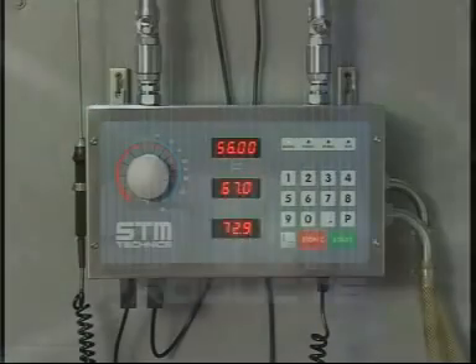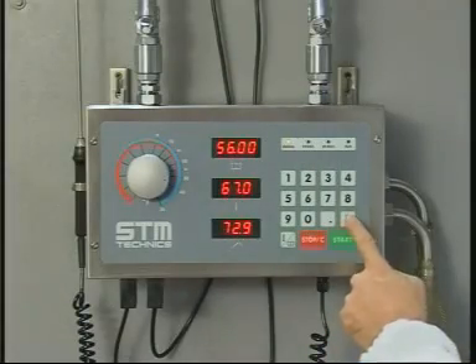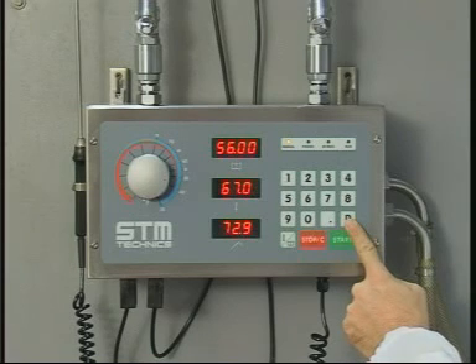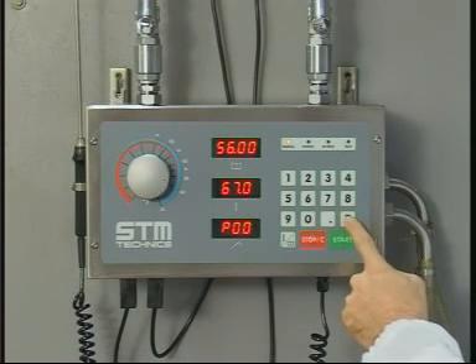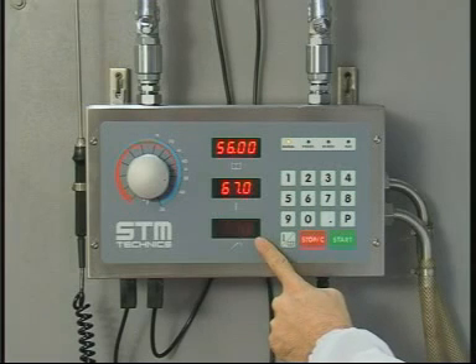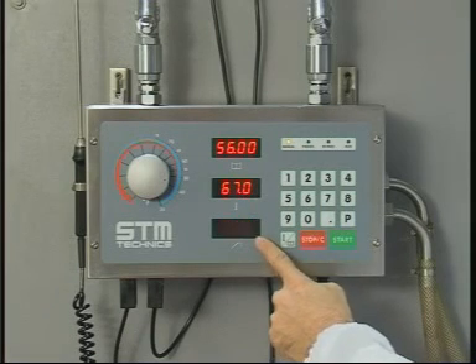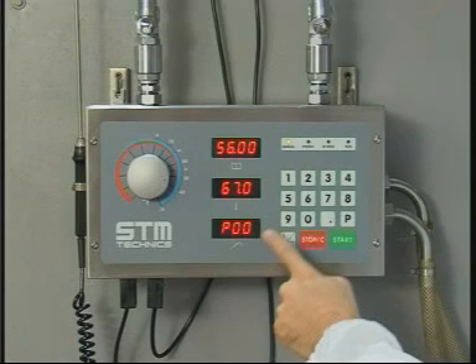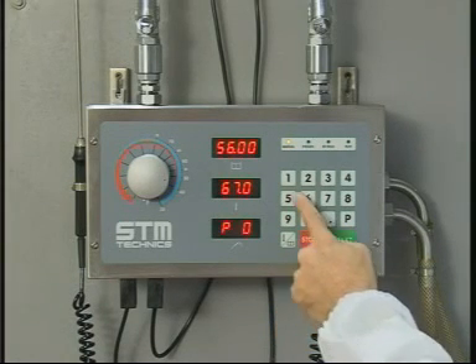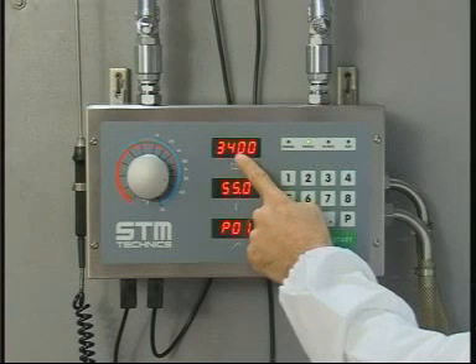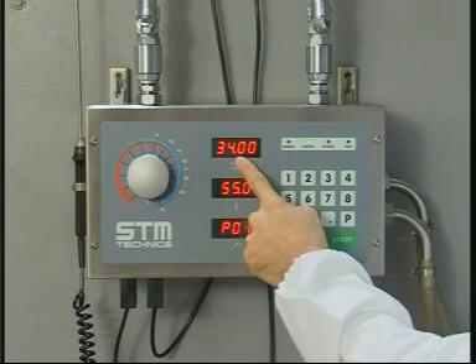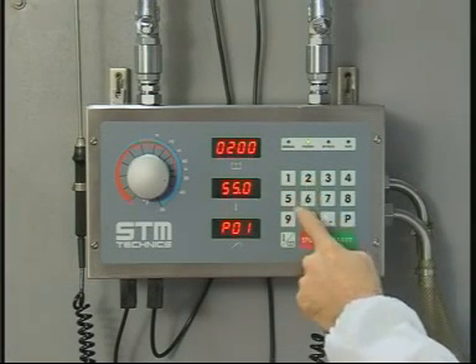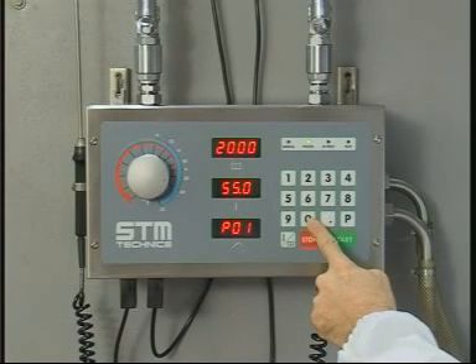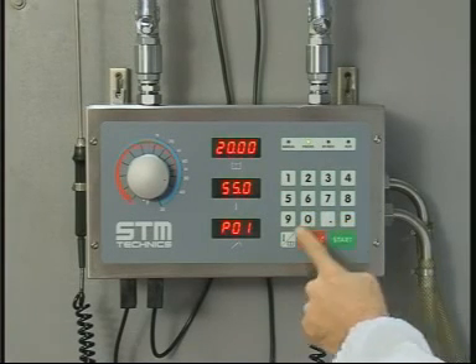Operation with recipes. To insert a recipe and to operate the machine in mode with programs, press key P. At this point, the lower display begins flashing, and with the keyboard, a program or recipe number from 1 to 80 can be set. By pressing the quantity temperature key, the decimal point of the upper display begins flashing, and the desired quantity can be programmed.